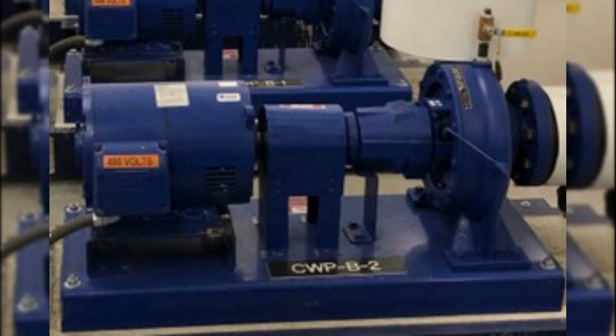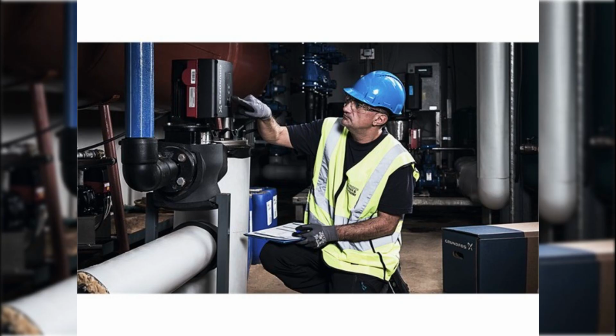Finally, every piping connection needs to include valves, strainers, pressure gauges, and flexible connectors to ensure smooth operation, proper monitoring, and long-term reliability. Before the pumps go into full operation, both pre-startup and startup tests must be carried out, and these have to be witnessed by factory representatives. Once the tests are complete, the contractor is required to submit affidavits confirming that everything has passed. Next comes functional performance testing, which verifies that the pumps integrate properly with the building management system, that alarms trigger as expected, and that all control sequences operate correctly.